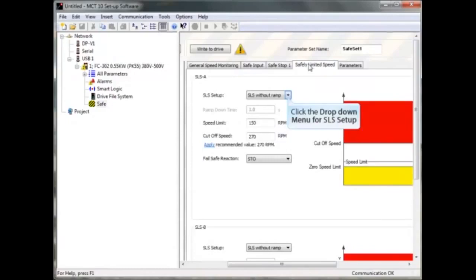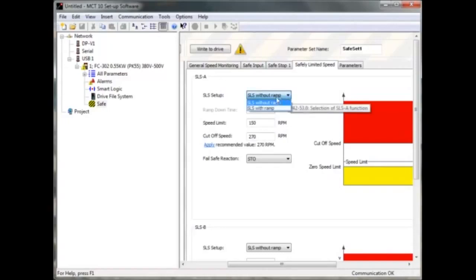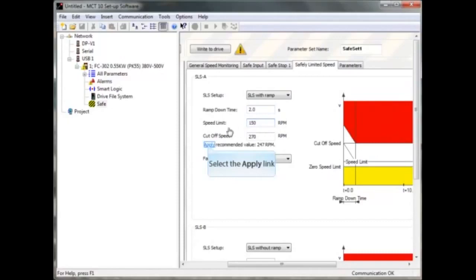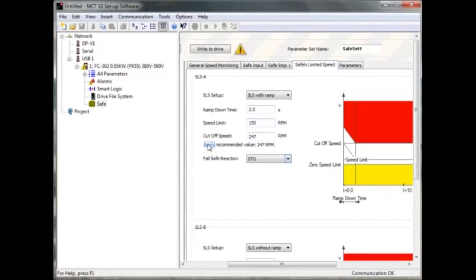In the last sheet you configure your safe limited speed settings and set the fail-safe reaction. You can choose SLS with or without ramp. Choose a ramp-down time and set the speed limit you want for the SLS speed. For the cutoff speed, take the recommended value and press apply. The safe failure reaction you can choose is STO or SS1.